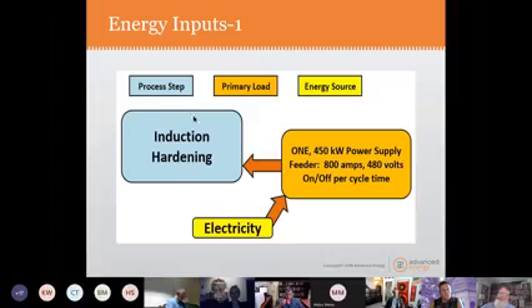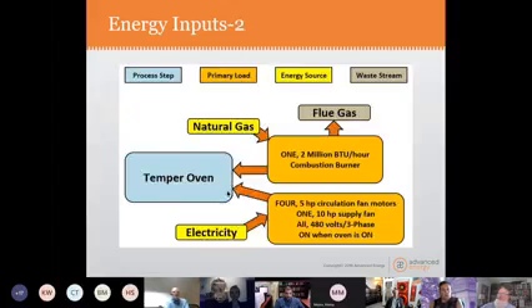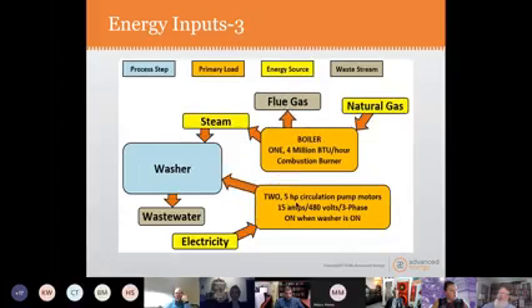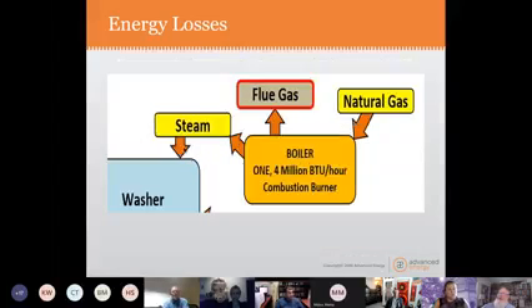I've just got a few examples. Maybe you have an induction hardening process, so you have an electrical power supply and electricity feeding that. You probably have an oven where you temper these metal parts, so you have natural gas combustion, you have flue gas, you have electricity running the fans to circulate the heat in the oven. You kind of get the idea. If you spread this out across an entire plant or a process, you have a washer to wash these parts after they've been manufactured and before you paint them. So you may have a boiler with steam to heat the washer, and some circulation pumps and so forth. In this case you have natural gas, steam, and electricity, and you map that out across the entire plant, and you get a good idea of where the energy is consumed, but also losses. If you have a boiler making steam, that hot flue gas is going up the stack.